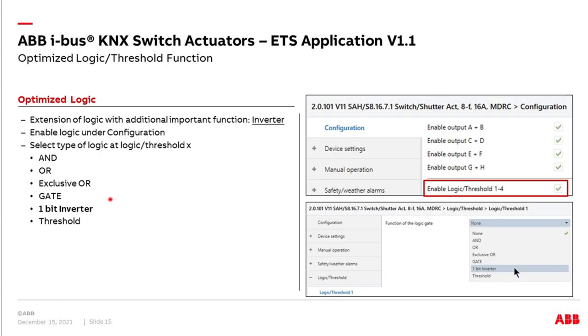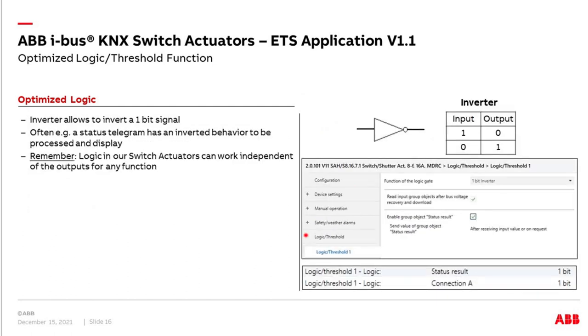What did we do in logic? We added a one-bit inverter. How to enable this is very simple — you have here six parameters, each enabling logic blocks, and then you decide what shall be selected as the kind of function. And you see now a one-bit inverter is available. It's not a very complicated function — in principle, inverting a one-bit signal from one to zero and vice versa. I have experienced that this is sometimes needed more than expected, because any status telegram sometimes has to be inverted in behavior to be processed. So a quick inverter is now directly in the Switch Actuator, and it's really independent of the outputs.